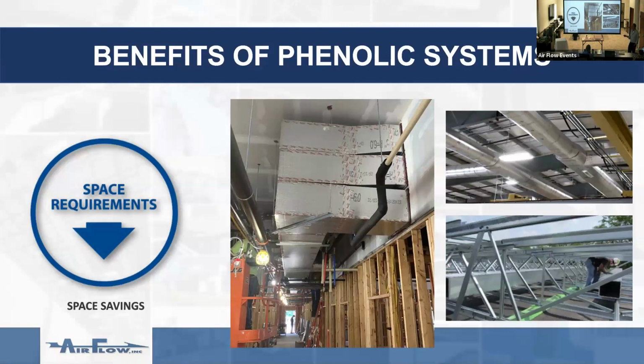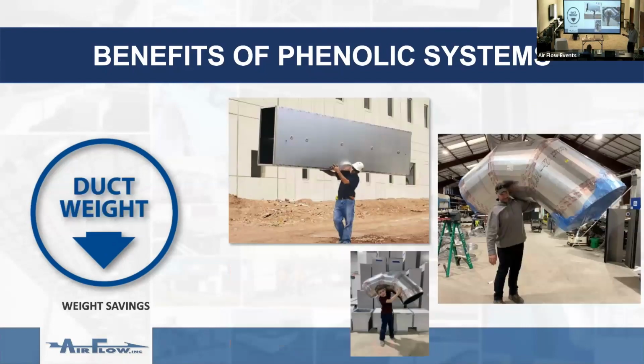You can see some of the benefit of having the ductwork and the insulation be the same. If you're in a tight space, you can put the ductwork adjacent. You can also build two or three ducts in the same box with a septum panel in between. So you can separate different zones, or have supply running one way and return the other way, or exhaust or something like that. In a case like this where you're trying to squeeze between trusses, you don't need to leave room for insulation. You can lay it right on top of a metal or raise it right up to a deck. So you can get away with some stuff that you can't with metal, which is kind of cool. Most contractors want to put in metal, fine. This is a great fix for a really tight space. It's super light. Look at that kid. He would have fallen over and it would have hit him in the head.